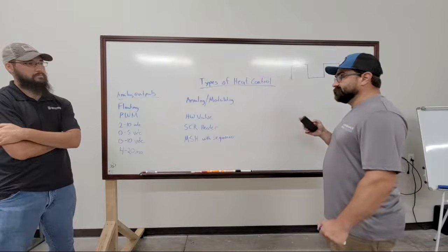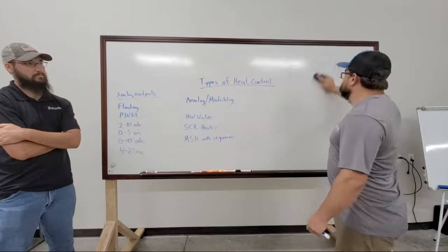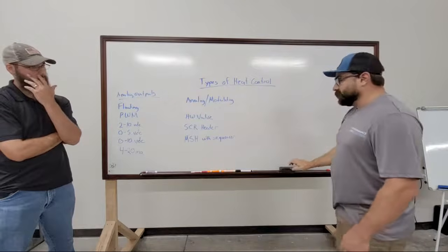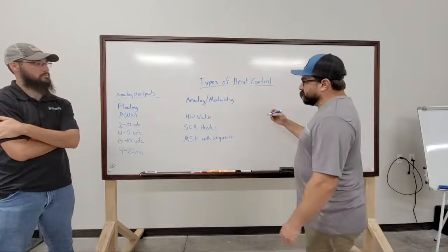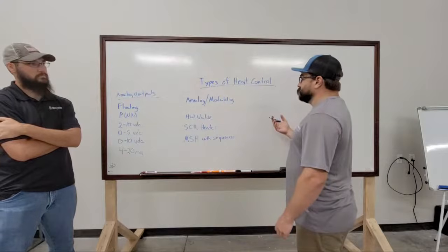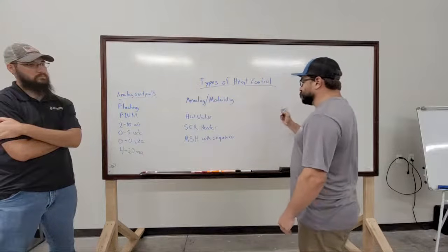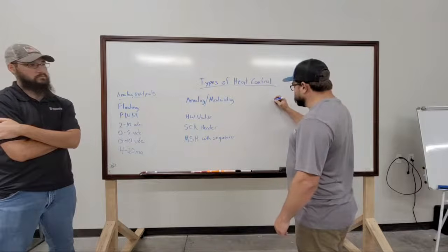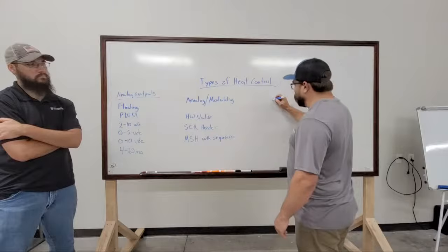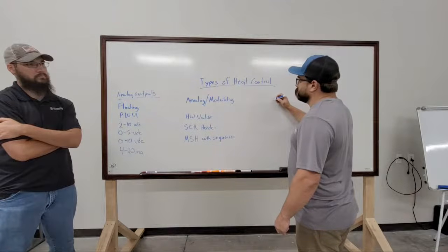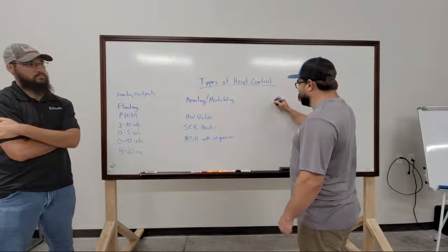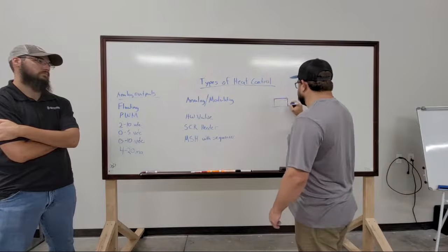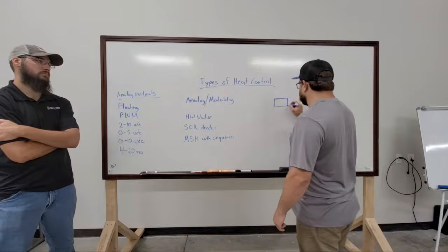And what's really funny is if you wanted to control that specific SCR I was dealing with, which was a Viconics, if you did not have a controller that could do pulse width modulation, you could, in theory, use a digital output and I guess a VDC transformer. So this would be your solid state relay in your controller.